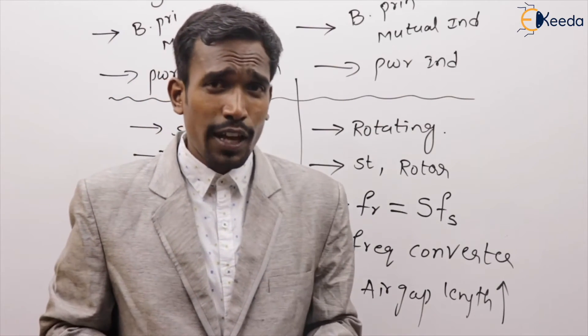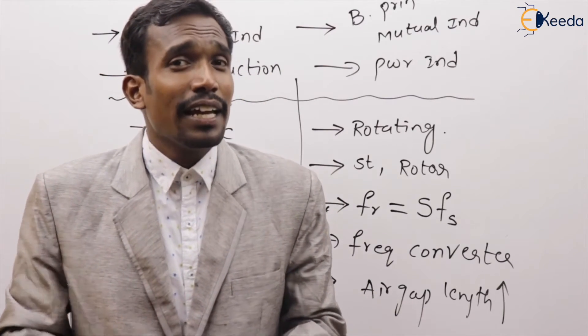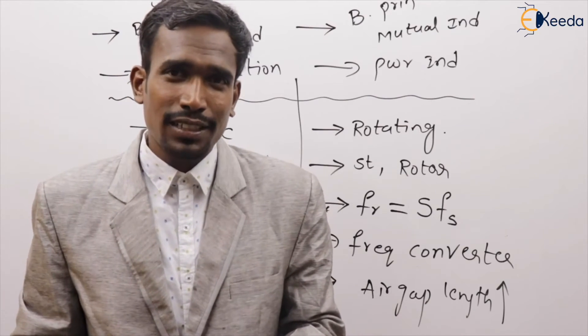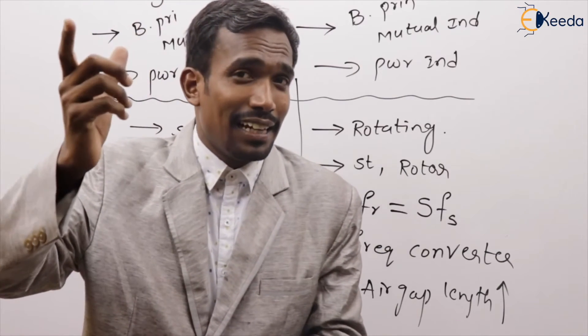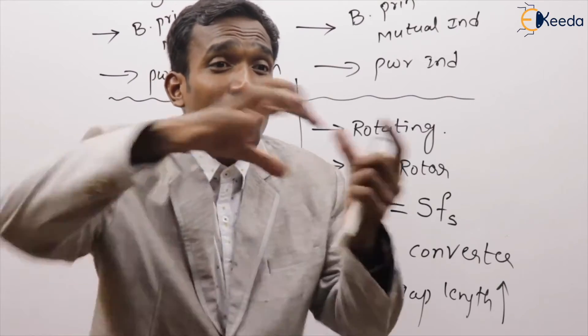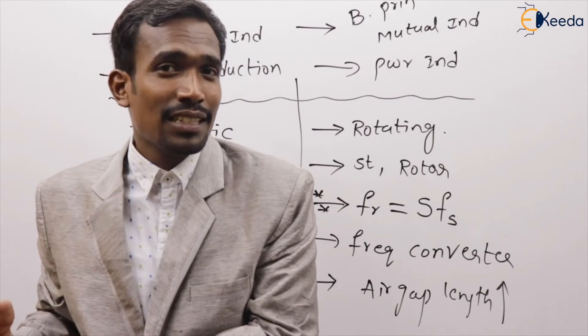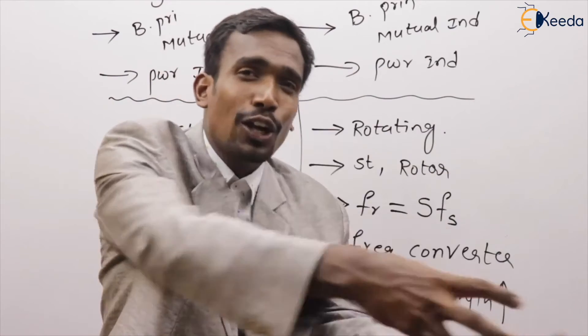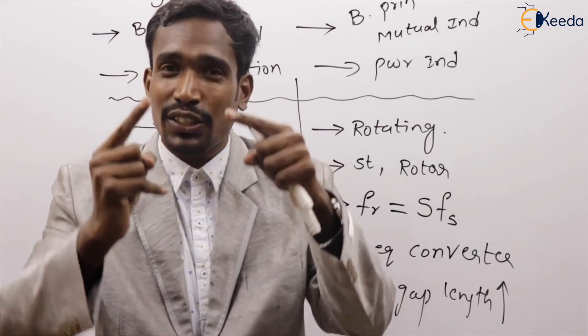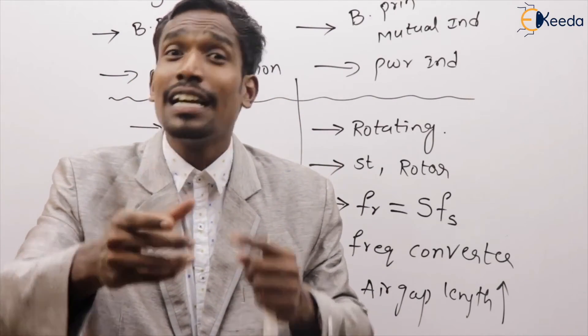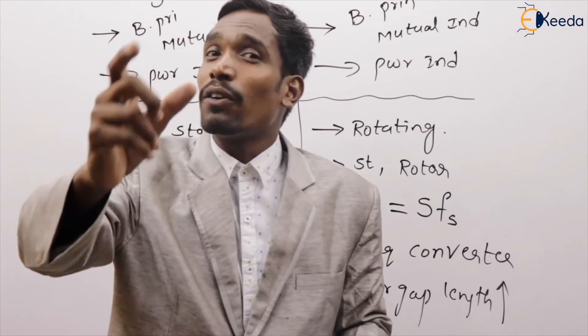If the air gap length increases in any electrical machine, it draws more magnetizing current. When magnetizing current increases, the no-load current increases. If no-load current increases, the power factor reduces. This is a very important point: in any electrical machine, if air gap length increases, power factor reduces.